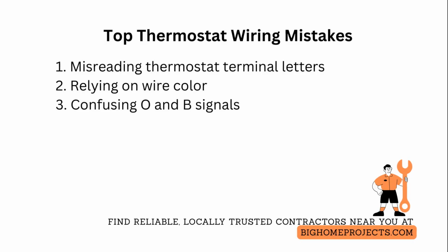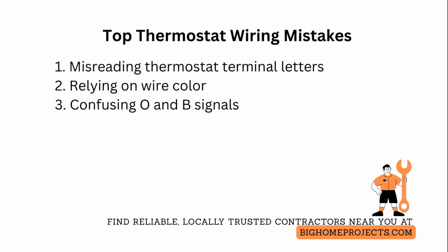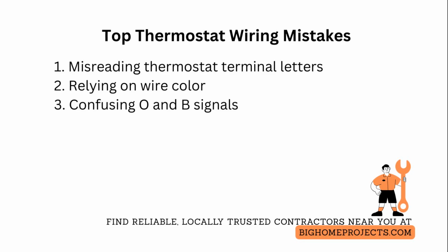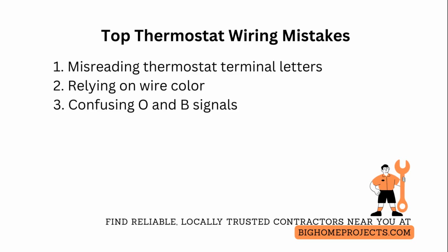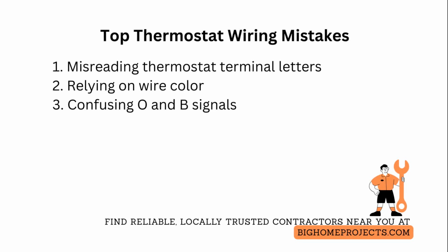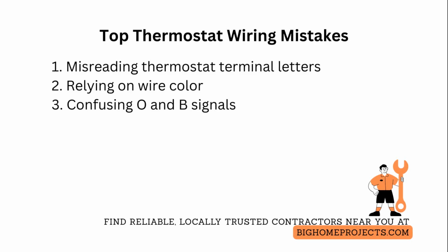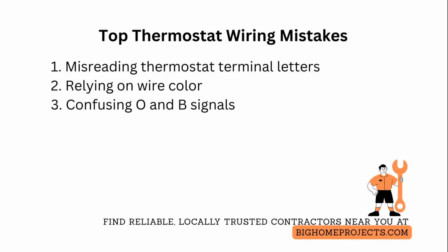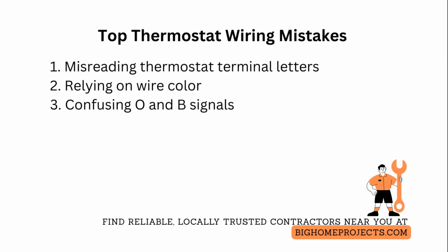One of the most common thermostat installation mistakes is misreading thermostat terminal letters, leading to no heat or no cool. Fix this by photographing labels, verifying terminals on the control board, and testing functions one at a time. One of the next frequent errors is relying on wire color instead of lettered terminals, which can short compressors or blow control fuses. Remedy that by labeling wires, tracing them to the control board, and using a continuity check if wires are bundled or long.